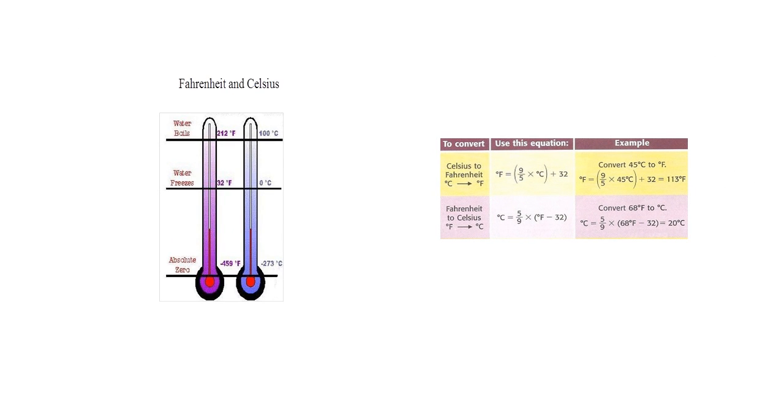The two most common temperature scales used in the HVAC industry are the Fahrenheit scale and the Celsius scale. They are based on the melting of ice and the boiling of water at sea level. It is important that you are able to convert between the two scales. If in the picture of thermometers they were to show all the hash marks between the temperature ice melts and water boils, the Fahrenheit thermometer would have 180, while the Celsius would only have 100. So for 5 marks on the Celsius scale, you have 9 on the Fahrenheit scale.